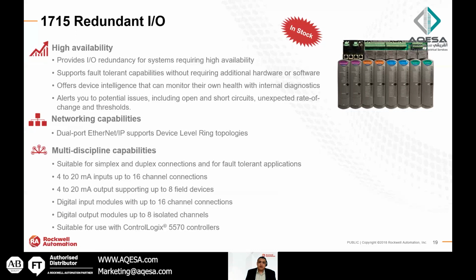1715 redundant IOs. This one is in stock in Saudi Arabia. You can get immediate delivery. Before these IOs, we used to have dual redundancy using 2 chassis of ControlLogix and termination boards, and programming was a little tricky. With this family, 1715 redundant IOs, you can get the wires from the field up to here, and the signal is duplicated inside this terminal base. The redundancy is handled by the firmware. So if one module is down, the other is there. It will be handled automatically by the firmware.